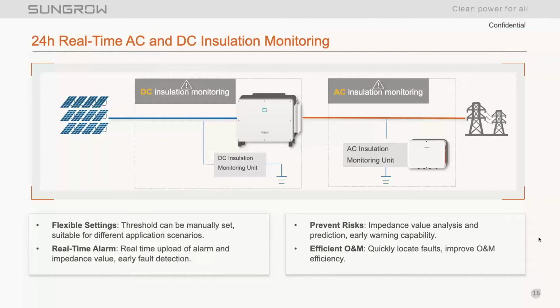The addition to this is that we're going to be offering that same type of monitoring on the AC side, to do AC insulation monitoring on the cables that are connected to the AC wiring box on the side of the 350. So that's also going to reduce the amount of equipment that's necessary on the secondary side of a medium voltage transformer. So we're going to be really reducing the amount of CapEx consideration in a project that's going to incorporate the 350. And all of these thresholds can be manually set, right?